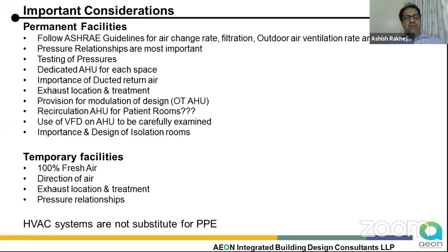We saw some examples of recirculation air handling units being used for the patient rooms. I think again, when we are trying to convert them into isolation rooms, each of the patient rooms or the IPD areas, we found such systems lacking, and they need to be carefully examined going forward. And finally, the isolation rooms, it's very interesting. I may be designing 40, 50 healthcare units. Most of them, we still don't know till the point the final designs are being done, are we going for a positive isolation room or a negative isolation room? It's all left very vague. I think the design and the importance of the isolation room, including the ante room and all, have come out.